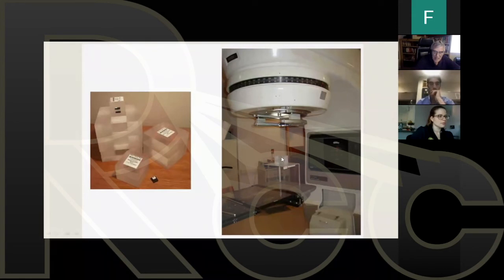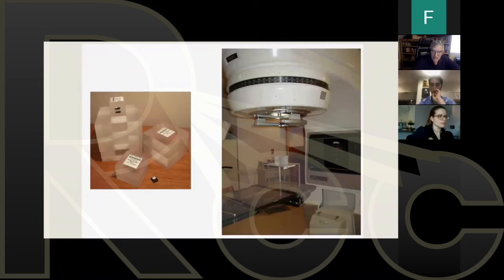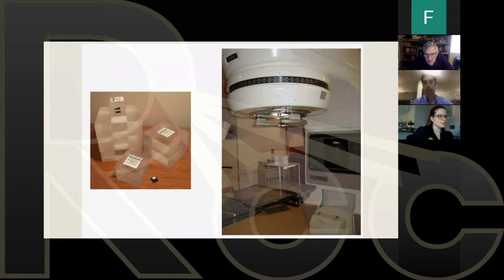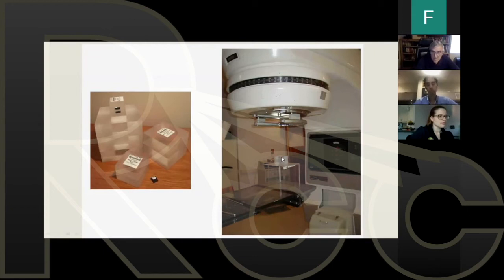The TLD is embedded in the block, and what the IROC says to do is deliver 100 centigray to this block with a 10 by 10 field, 100 SSD. So they give you the distance, the field size, they tell you the dose to deliver, and they tell you at what depth. They want it at D-max. So the maximum depth dose is where you calculate this for. So using your table and your adjusted output, what you think is the correct output of that machine, you give 100 centigray at 100 SSD, 10 by 10 field, D-max. And they will tell you in a week or two exactly how much dose you gave to that. And that is your reassurance that you've calibrated the machine correctly.